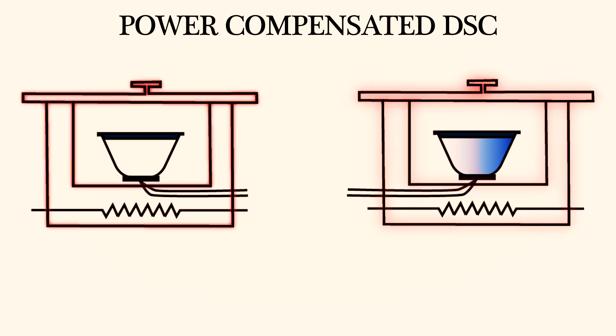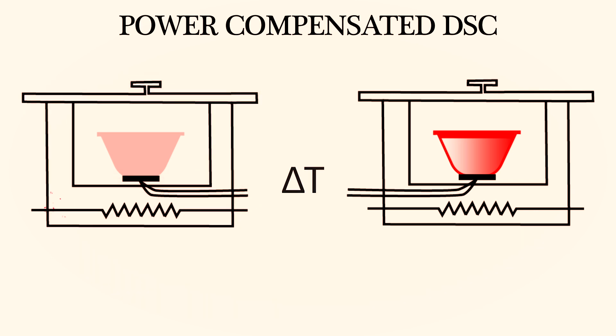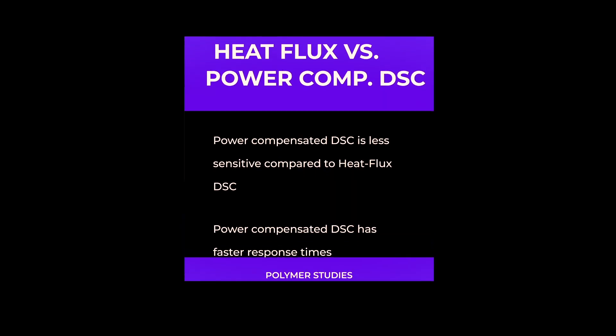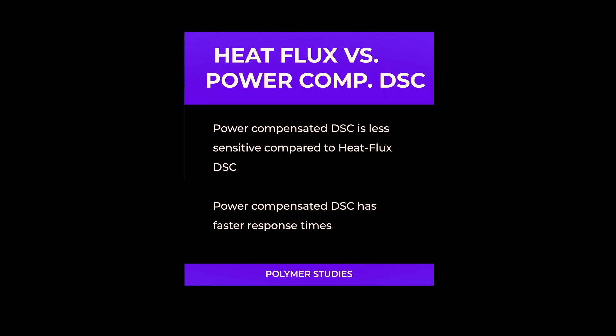Once again as the furnace is heated, the sample calorimeter lags behind the reference calorimeter due to its mass. The sensors capture this temperature difference and send an increased power onto the sample heater to minimize this temperature difference. The instrument records power difference needed to maintain the sample and reference to the same temperature as a function of program temperatures. Power compensated DSC is less sensitive compared to heat flux DSC but it has faster response times, which is why it is used for kinetic studies in polymers.